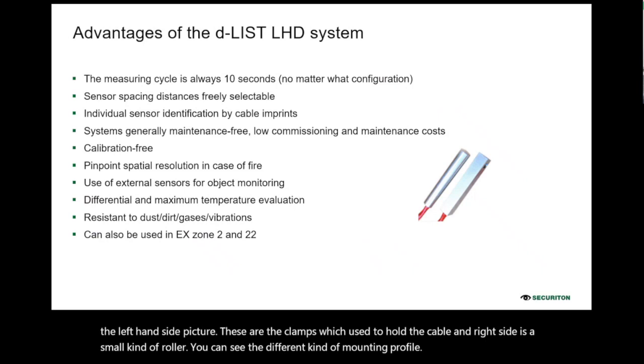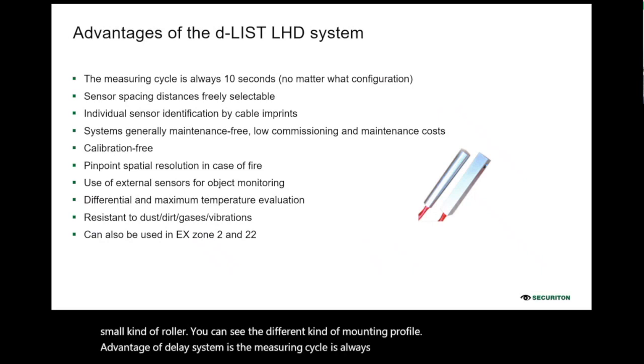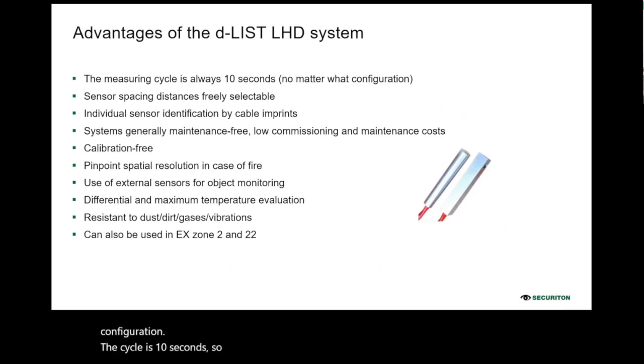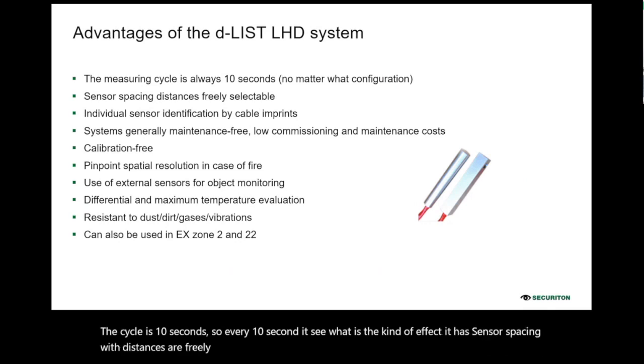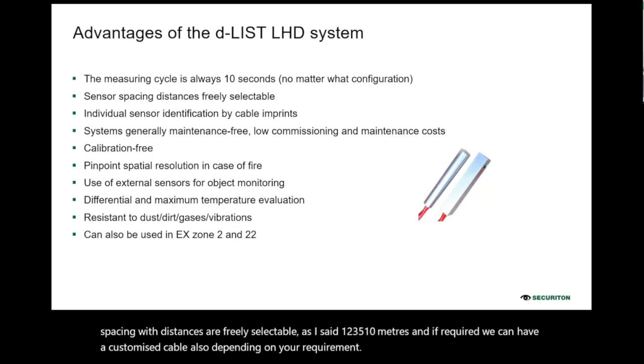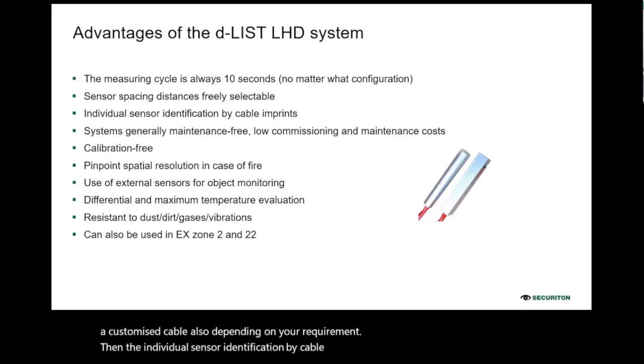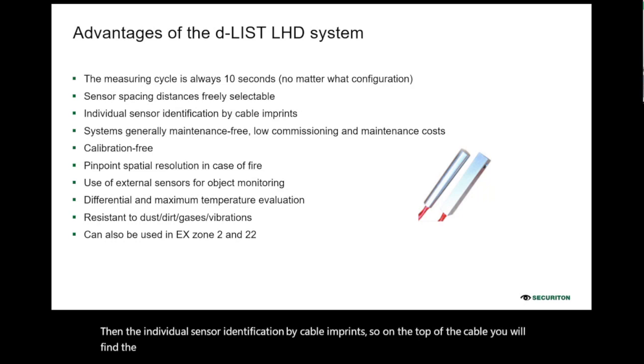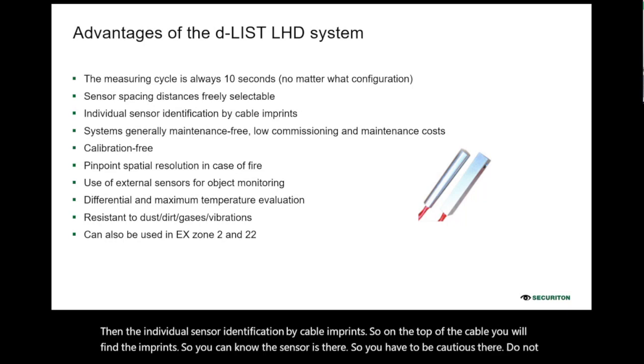The advantage of the dLiST system is that the measuring cycle is always 10 seconds. No matter what the configuration is, the cycle is 10 seconds. So every 10 seconds it checks what effect there is. Sensor spacing and distances are freely selectable, as I said: 1, 2, 3, 5, 10 meters. And if required, we can have a customized cable also, depending on your requirement. Then there is individual sensor identification by cable imprints. On the top of the cable you will find the imprints, so you can know where the sensor is. You have to be cautious there. Do not bend that sensor 90 degrees.